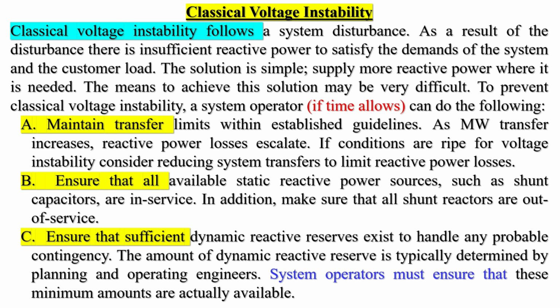A. Maintain transfer limits within established guidelines. As MW transfer increases, reactive power losses escalate. If conditions are ripe for voltage instability, consider reducing system transfers to limit reactive power losses. B. Ensure that all available static reactive power sources, such as shunt capacitors, are in service. In addition, make sure that all shunt reactors are out of service.